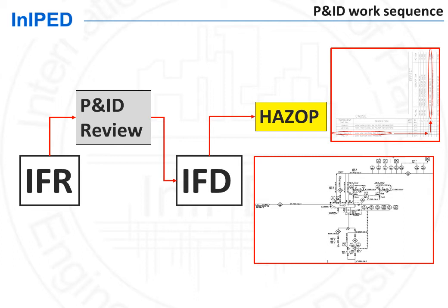These safeguards will be added on the next revision of the P&IDs, called the Issued for Construction revision. This issued for construction revision will also incorporate interface information from equipment vendors, such as utility lines, size of piping connections, including drain lines, vent lines, and so on.